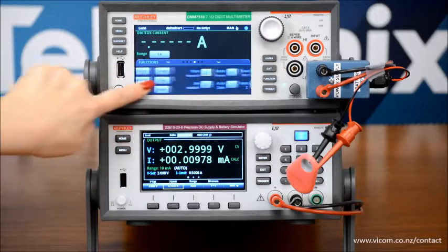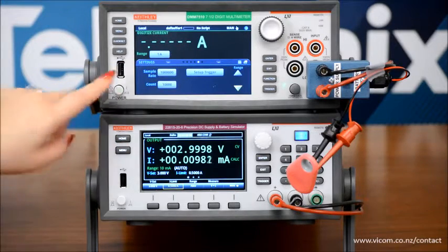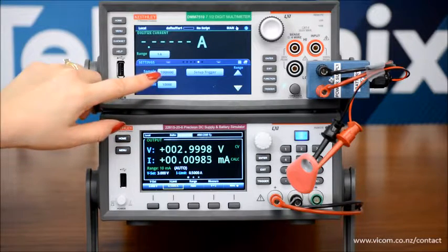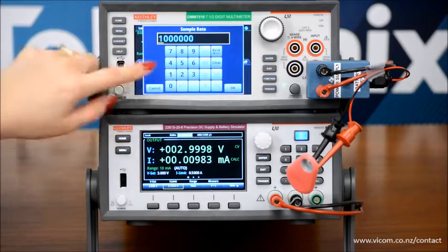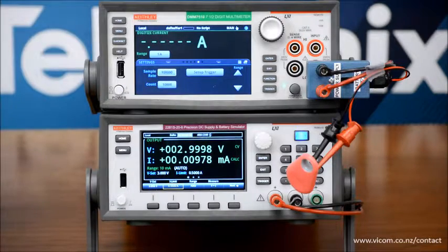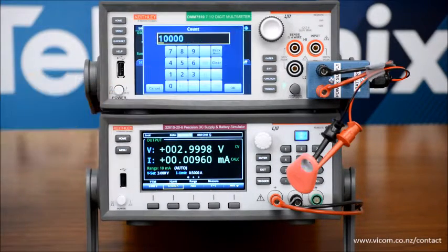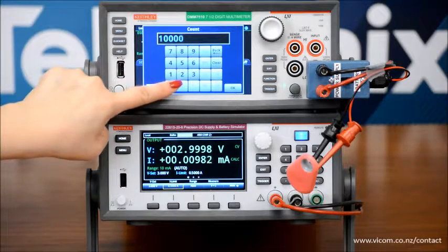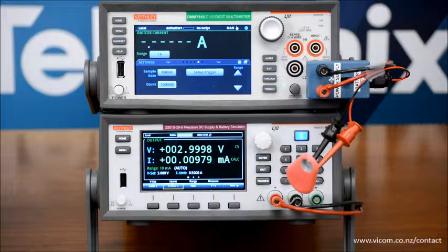Swipe the screen on the bottom. Change the sample rate from 1 megasamples per second, which is the maximum what this DMM can do, to 100K. And change the count to 1 million to match the buffer capacity that we just set. So with 1 million readings, that's 10 seconds of data at 100 kilosamples per second, or 10 microseconds per sample.